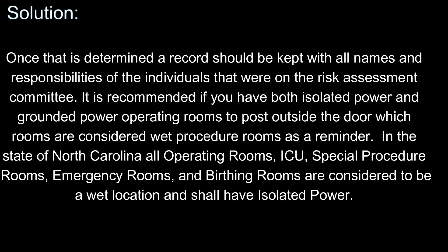In the state of North Carolina, all operating rooms, ICU, special procedure rooms, emergency rooms, and birthing rooms are considered to be a wet location and shall have isolated power.